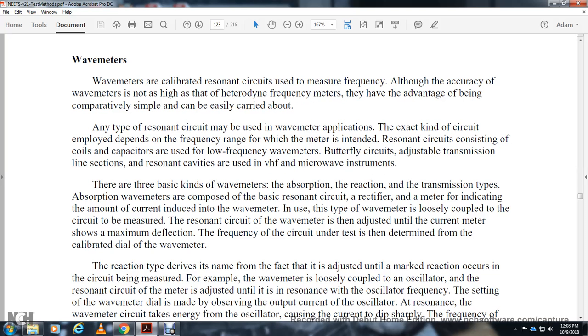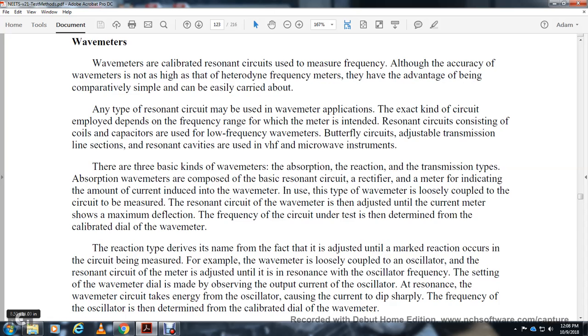The absorption wave meter is coupled with a basic resonant circuit, and the current is rectified with a meter indicating the amount of current induced in the wave meter. This type of wave meter is loosely coupled to the circuit to be measured. The resonant circuit of the wave meter is then adjusted until the current meter shows the maximum deflection. The frequency of the circuit under test is determined with the calibrated dial of the wave meter.